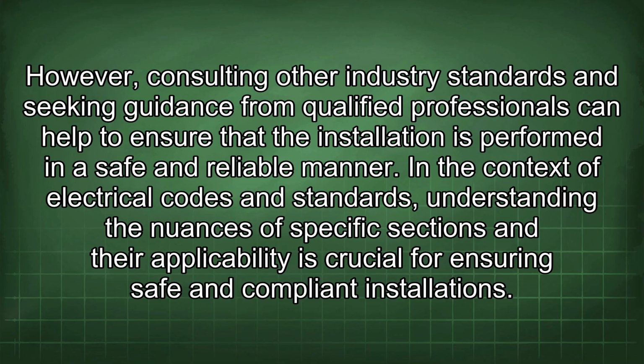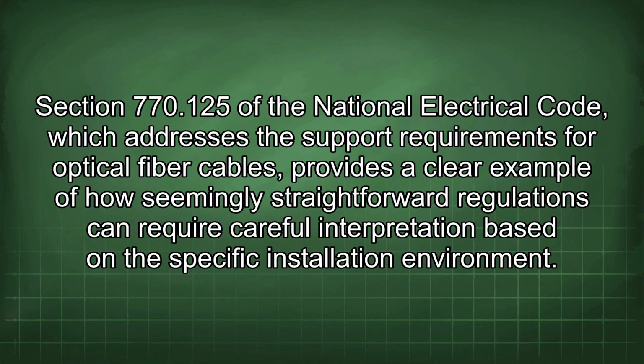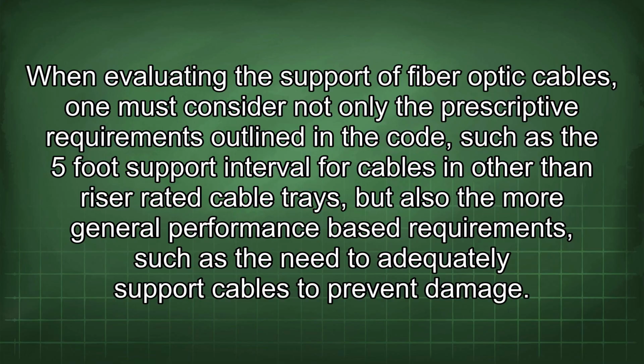In the context of electrical codes and standards, understanding the nuances of specific sections and their applicability is crucial for ensuring safe and compliant installations. Section 770.125 of the National Electrical Code, which addresses the support requirements for optical fiber cables, provides a clear example of how seemingly straightforward regulations can require careful interpretation based on the specific installation environment. When evaluating the support of fiber optic cables, one must consider not only the prescriptive requirements outlined in the code, such as the 5-foot support interval for cables in other than riser-rated cable trays, but also the more general performance-based requirements, such as the need to adequately support cables to prevent damage.